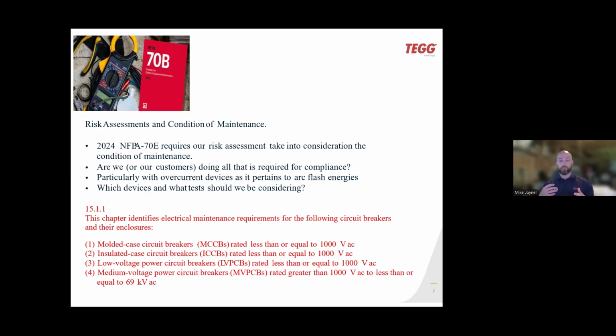So it's very imperative to go inside and make sure that these switchgears, these molded-case breakers, everything inside there is cleaned out, tested properly, and re-lubricated. If these molded-case breakers, these insulated-case breakers, are not properly lubricated, the lubrication inside there acts like a glue, which we're going to get into in the next couple of slides. So, Scott, you want to go to the next one?